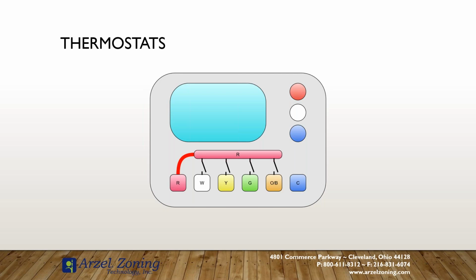Now, that's another reason where I like to use the resistance check, because I had a technician once that had a bad thermostat, and when he got out to the customer's home, he rightly diagnosed it as a bad thermostat. However, he replaced the thermostat and things still weren't working. So he went to the Arzel zoning panel and checked things there, and it was in the Arzel zoning panel if he jumpered around the thermostat worked. So he put his second thermostat on there, figuring he had a bad one off his truck. But still, that one didn't work either.